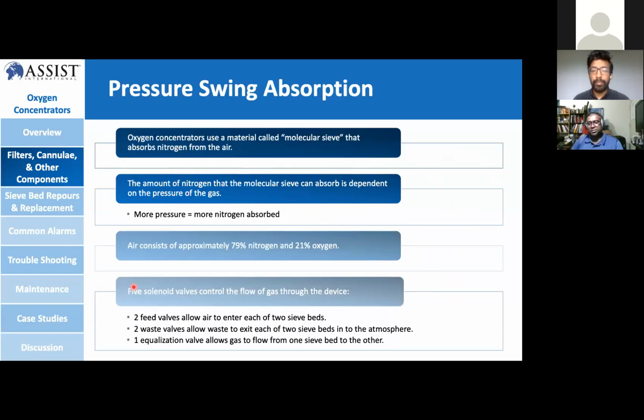Pressure swing adsorption is almost a similar thing. I'm going to repeat certain things that you need to know. In the oxygen concentrator, the material that you use is molecular sieve, which some people call zeolite, that absorbs nitrogen from the air and releases oxygen. The amount of nitrogen the molecular sieve can absorb depends on the pressure that you give in the cylinder itself. The greater the pressure, the better the oxygen output. But at the same time, the zeolite itself has a limit on the percentage of oxygen it can release, depending on the type of zeolite in the sieve tank. So more pressure, more nitrogen is absorbed, and eventually you get a release of oxygen.